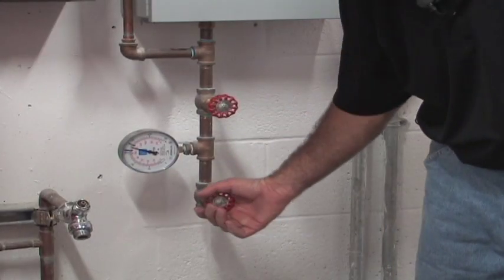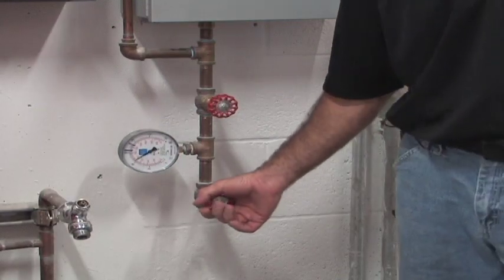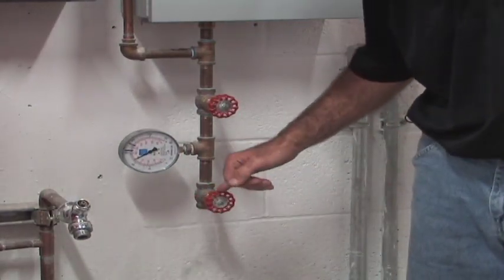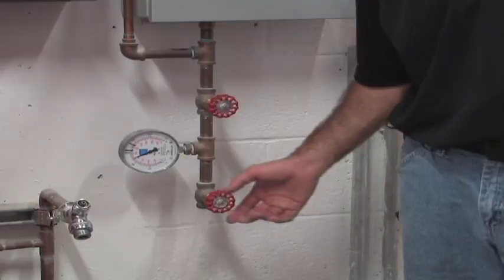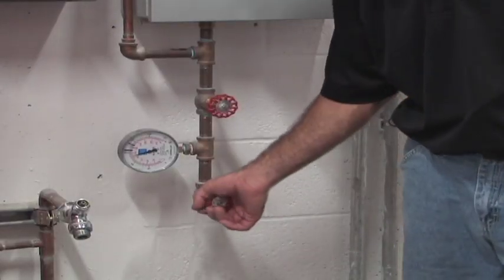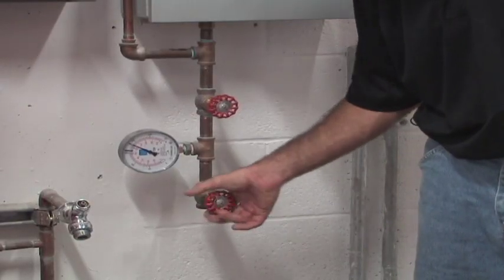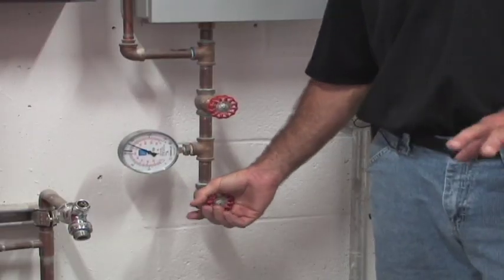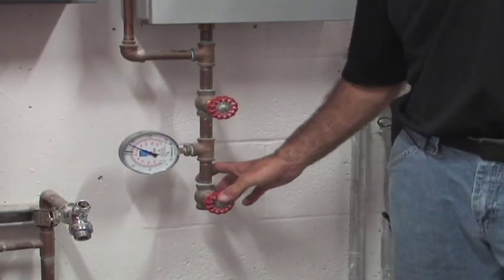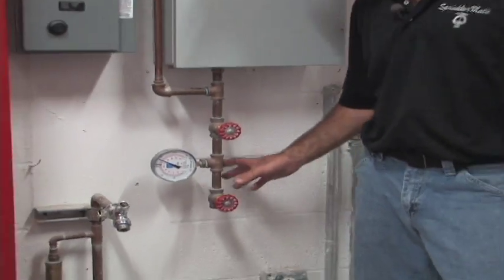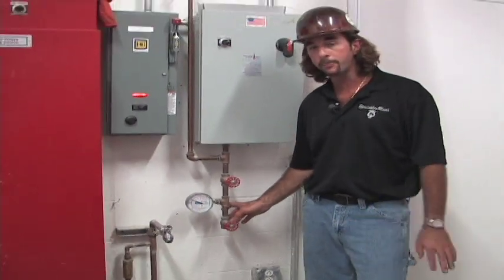Once it got up here, if you opened it a little bit more, it would stay running. As we shut this thing all off, like I said, we're going to get back to 180 psi and it's going to shut off automatically. That's how the system's going to work. This is how we test it or inspect it from here in the fire pump room.